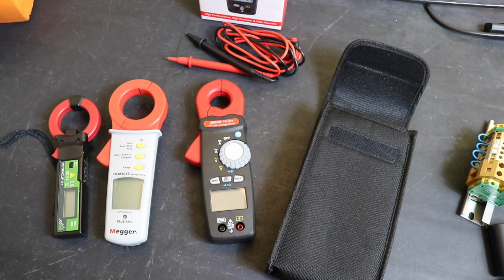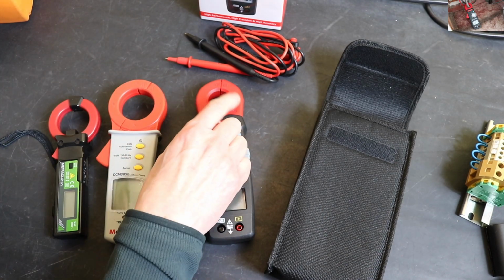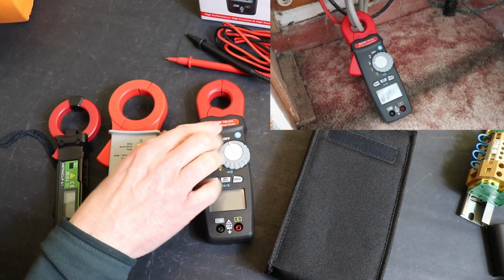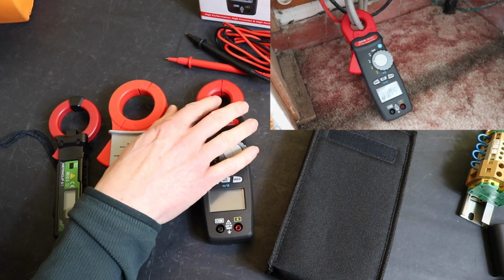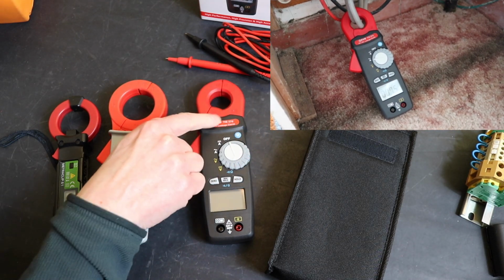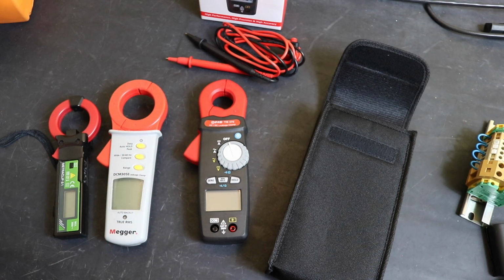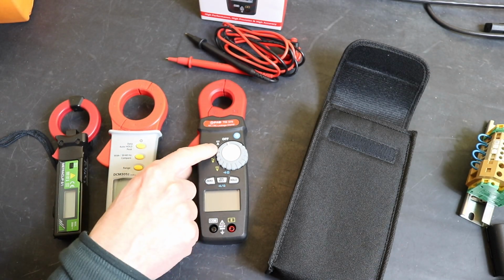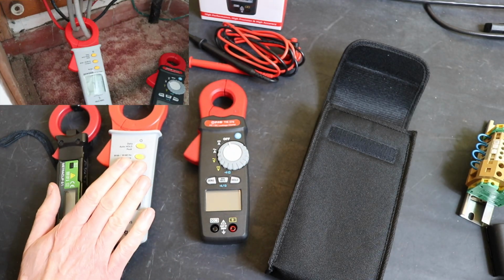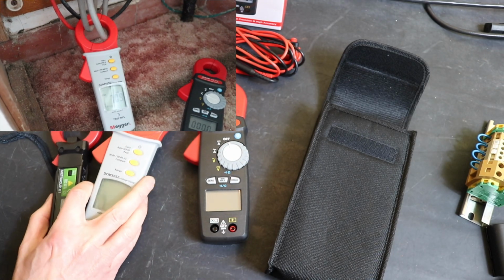So as I said, usually there's enough room in the tails, and you can get two tails through this, but if they're spaced quite tight and you can't pull the tails together, you might struggle getting this round when you're using the AC leakage current method and clamping around both tails. Not so much of an issue with these two here.